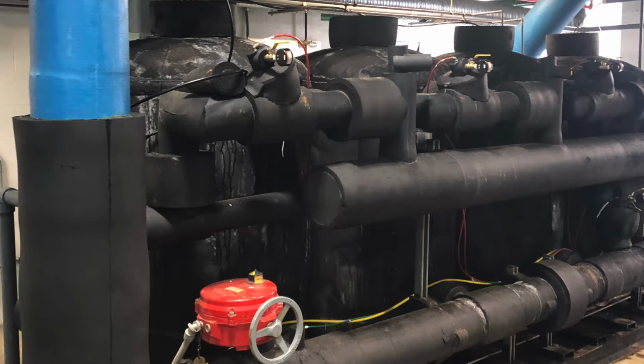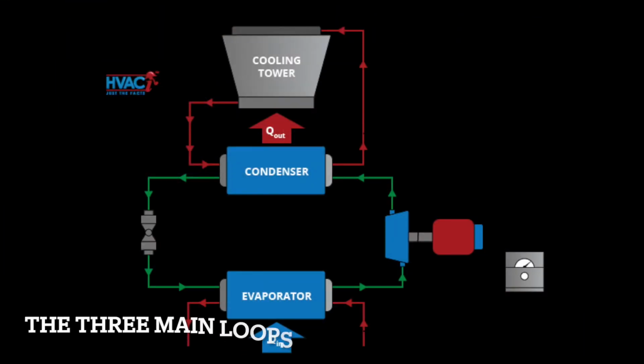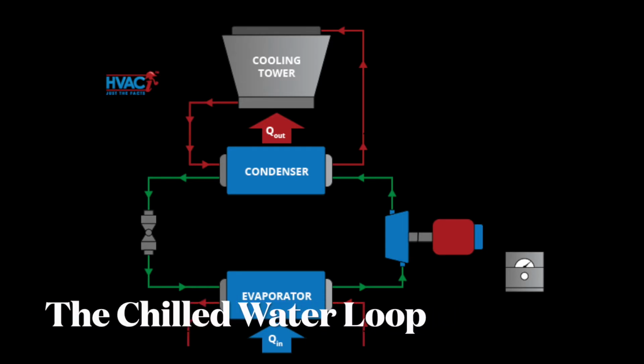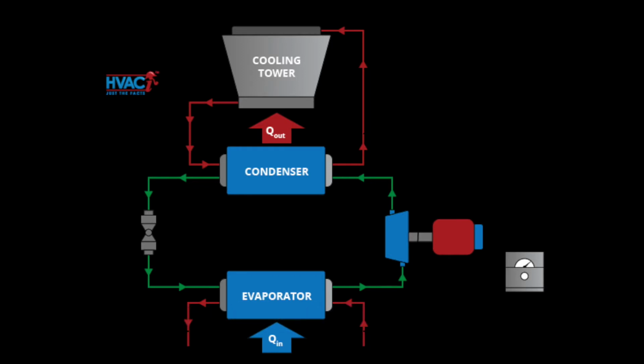There are 3 main loops that happen in the chilled water process: the chilled water loop, the refrigerant cycle, and the condenser water loop. The chilled water loop is a closed loop taking place between the buildings and the evaporators found inside the chillers, and it consists of potable water. In the beginning of the chilled water process, chilled water supply is sent out to the buildings scattered throughout campus. The buildings heat up the chilled water, and that newly heated chilled water returns back into the evaporators.